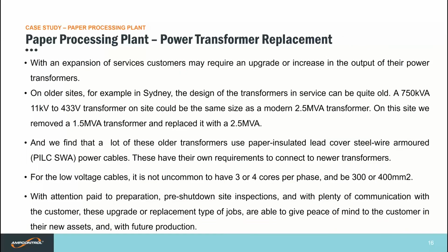Our last case study for the day was a paper processing plant where we replaced a power transformer. On site, they had an expansion of services, and with that expansion, they required an upgrade in the output of their power transformer. On older sites, for example in Sydney, the design of the transformers in service can be quite old. An older 750 kVA, 11 kV to 433 volt transformer on site could be the same as a modern 2.5 MVA transformer. On the site in this case study, we removed the 1.5 MVA transformer and replaced it with a 2.5 MVA.